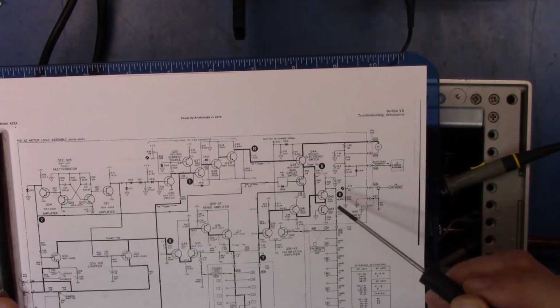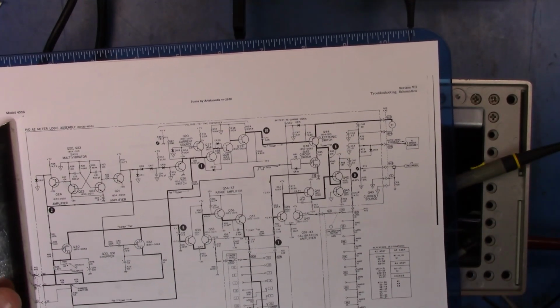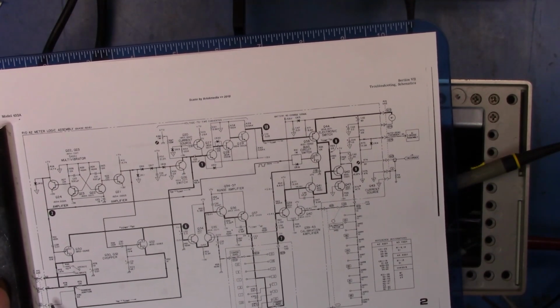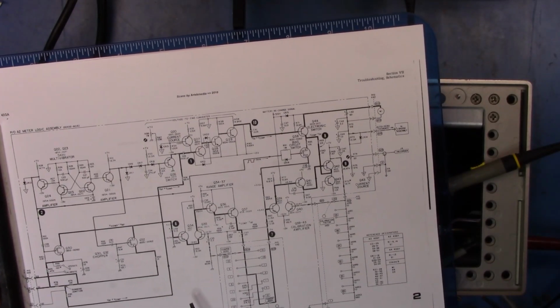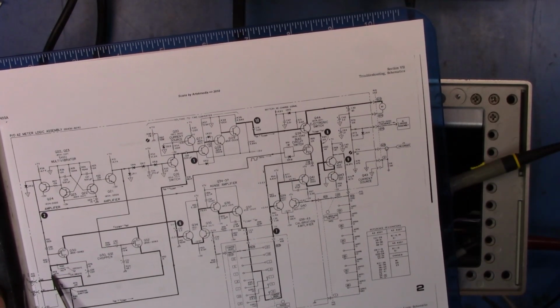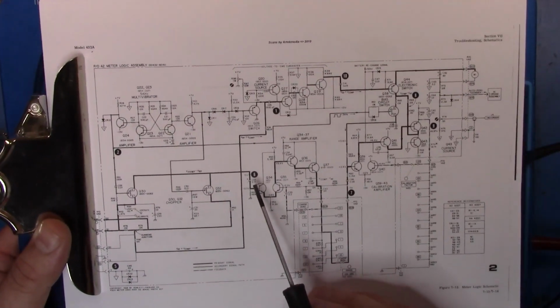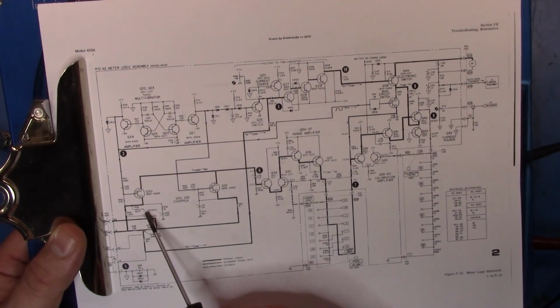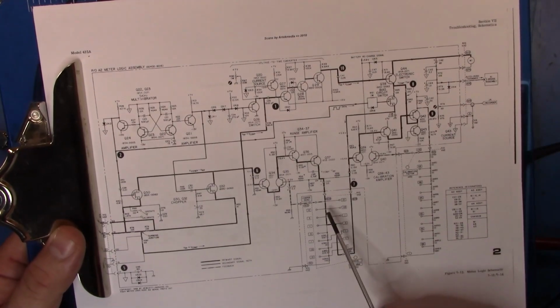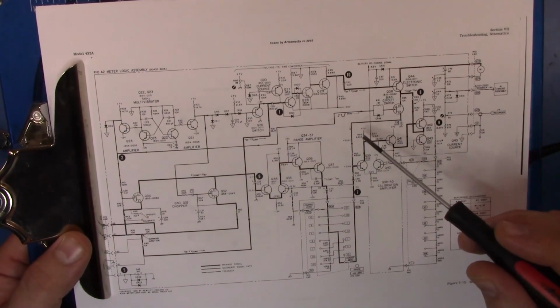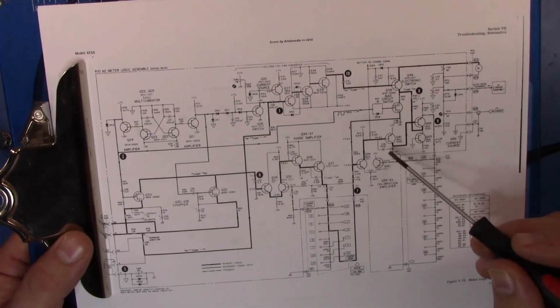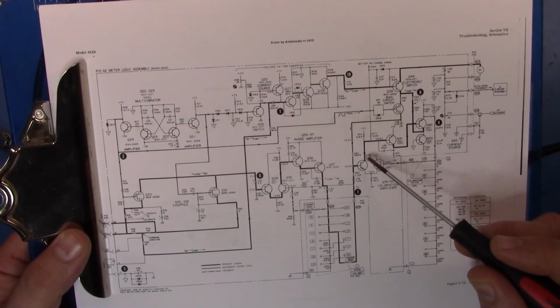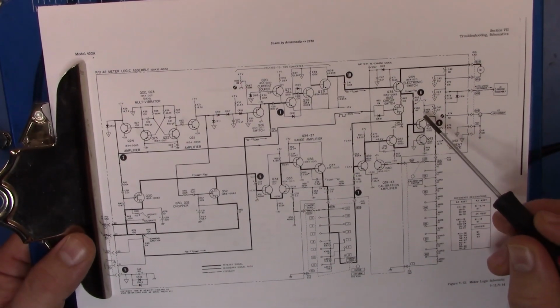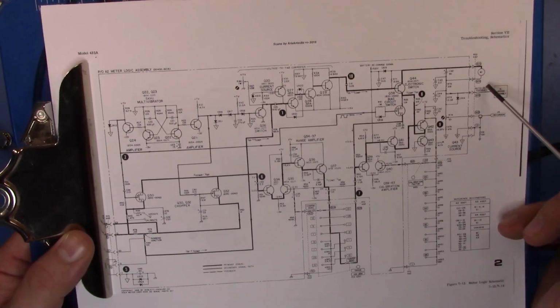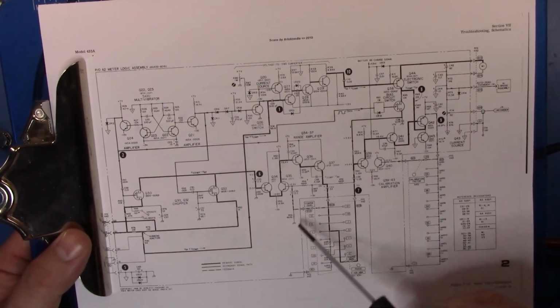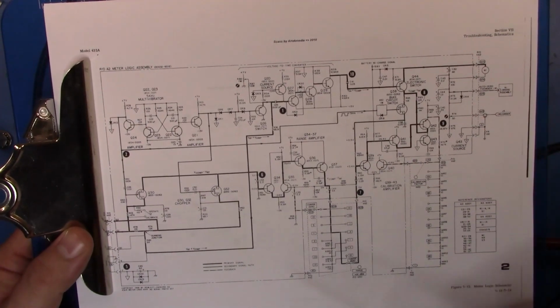9 isn't correct either. If we follow the incoming signal, what's coming in is through here, let me make sure I'm on it — it comes in through here, goes down, goes through the range switch, comes up here, goes through the calibration amplifier, then into that electronic switch, and then appears at the meter. The other path comes up through here and then goes in there.